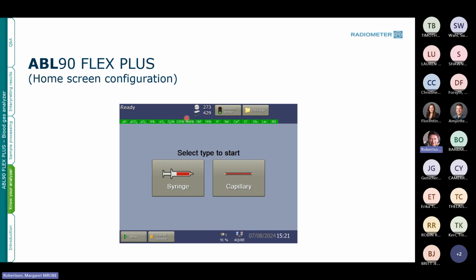This little group of icons up here shows you on the bottom the solution pack and how many determinations are left, and the sensor cassette and how many tests are left. The analyzer status button is probably the most important button on the analyzer because that's going to give you access to almost everything you're going to do with this analyzer. The next one is your data logs, and pushing the data log button will drop down a menu to give you access to QC, patient information, calibration, and other test methodologies we've got in here. You'll see that right now everything up there is green, so that means the analyzer is totally ready to go.